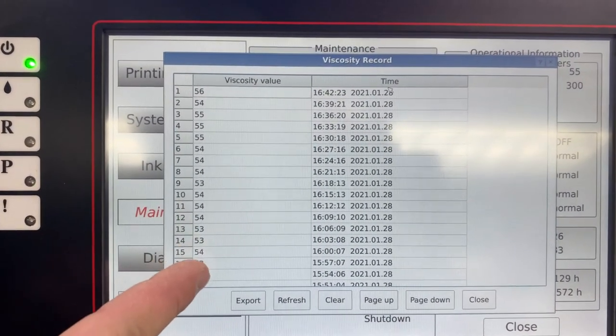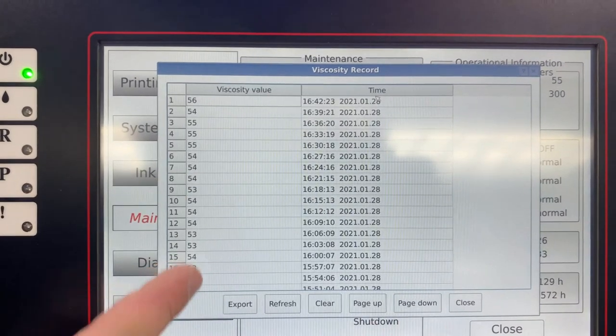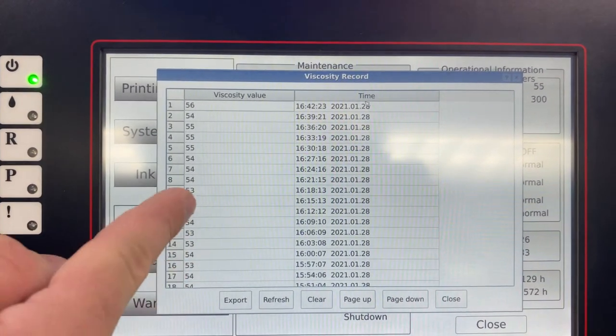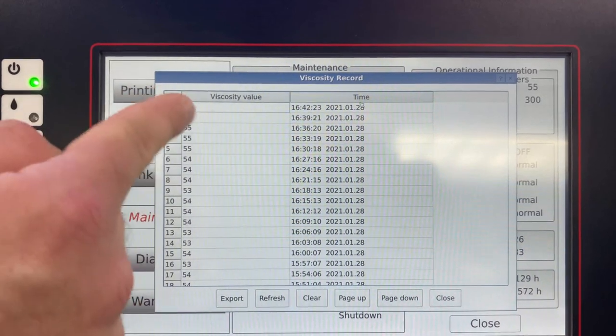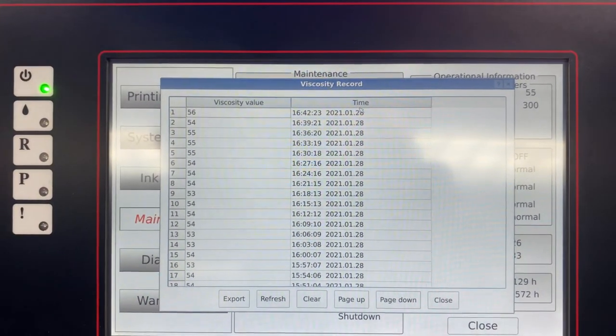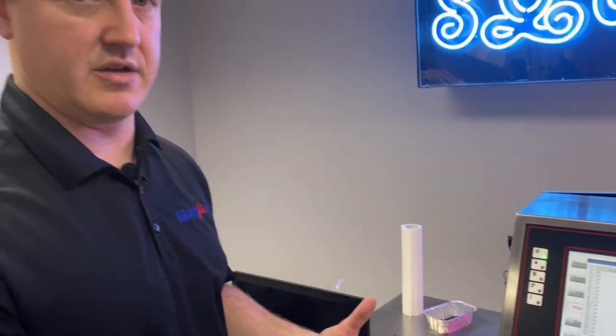But if we notice this number, the machine is checking every 3 minutes. So if we notice this number climbing every 3 minutes above 55, higher and higher, there's a very good chance we're not getting makeup from the cartridge to the mix tank to thin out that fluid and drop that number back down. In that scenario, that's when we would start troubleshooting the makeup circuit of the system.